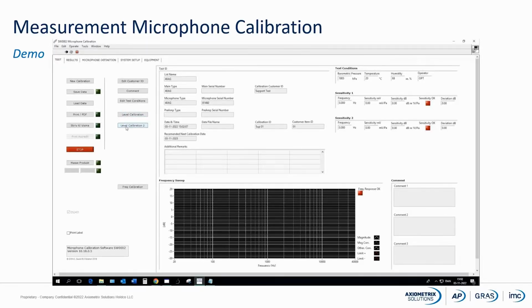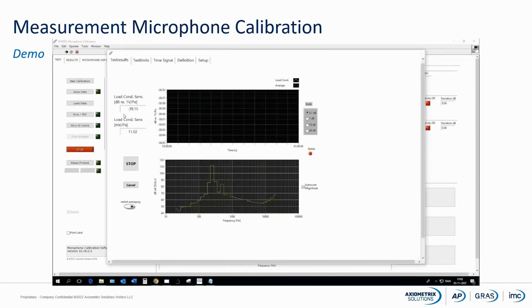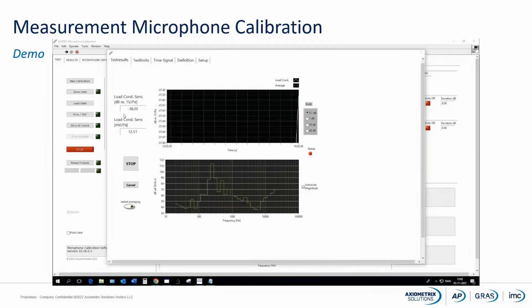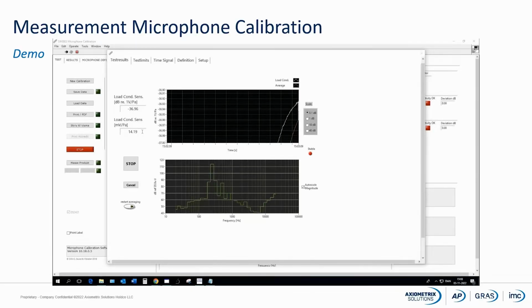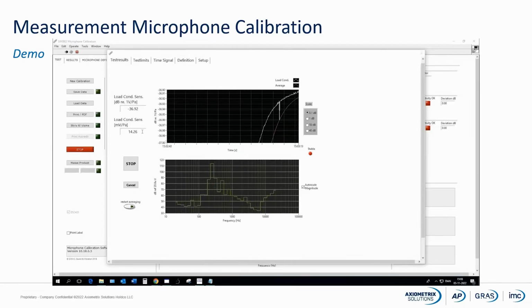Then we have two level calibrations. One is called level calibration 1, which is the reference where we use a piston phone. Level calibration 2 is where you can use a sound calibrator if you would like a level calibration, let's say at 1 kilohertz. But in this case, I will do my calibration with my piston phone at 250 hertz. So I will start the measurement, then the piston phone will start automatically, and we can see that the pressure is built up inside the little chamber, and the microphone starts to have the right sensitivity.